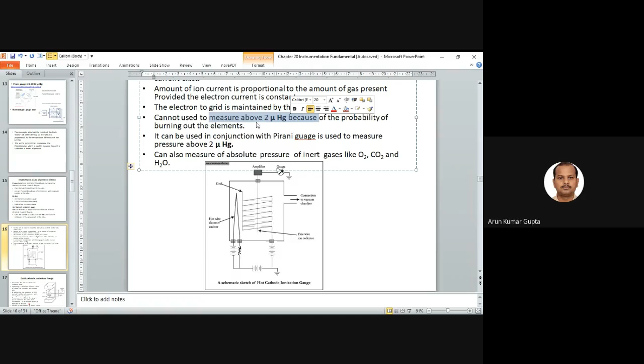In this we connect to the vacuum chamber, which is the source, the system whose pressure we want to measure. We have the fine wire ion collector, so the ions will be collected at this wire, and correspondingly we can get the readings. So it can measure very low pressure, at 2 micron mercury. It can also be used in conjunction with the Pirani gauge.